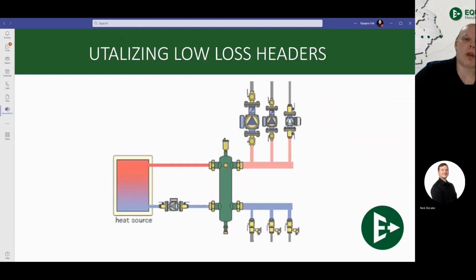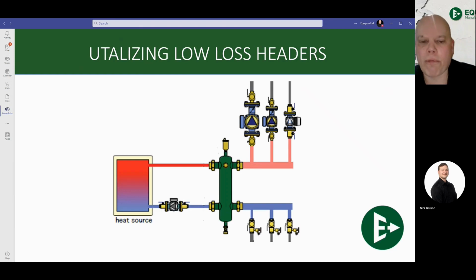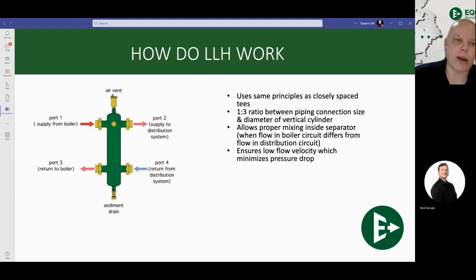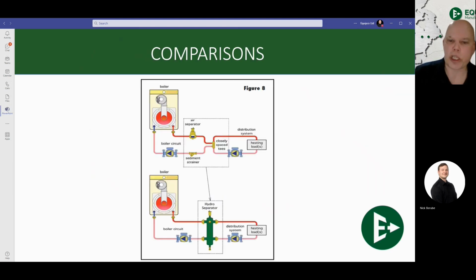Now, if we were to use a low loss header, we now have a boiler into our low loss header and back. No need for another additional high efficiency air separator in there. It operates on the same dynamic of closely spaced tees of no more than 4 pipe diameters apart, and it ensures that there's going to be a low velocity or low pressure drop between its two flows with regards to which way it's going to be flowing.